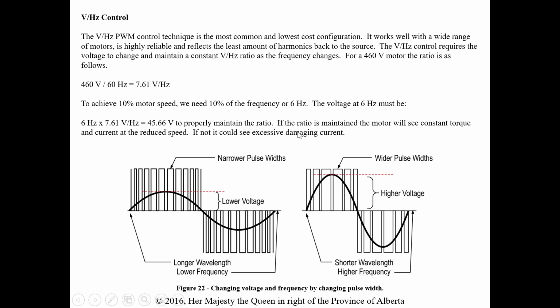If the ratio is maintained, the motor will see constant torque and current at the reduced speed. If not, we could see excessive damaging current. So what we want to do is basically maintain this volts per hertz ratio, and you guys will definitely have to calculate that in some questions we have coming up. But again, 10% is what it asks for. It could ask for 50% of the motor. Again, we would just take 50% of the frequency and then multiply that by the volts per hertz ratio and get the expected output voltage to properly maintain that ratio.